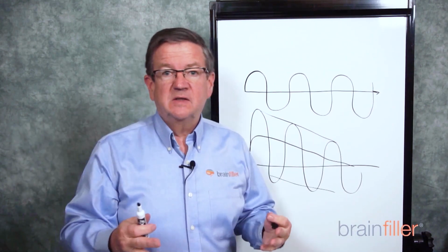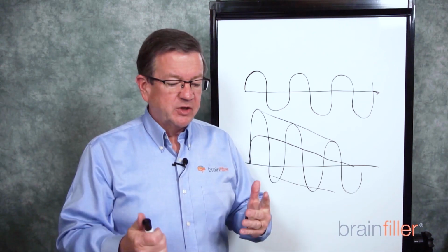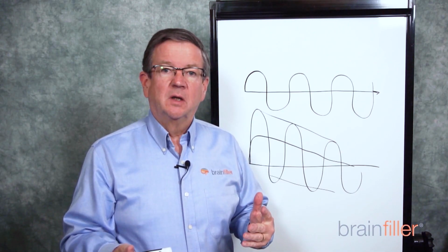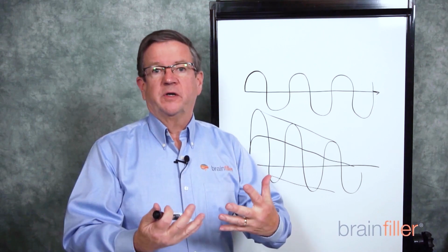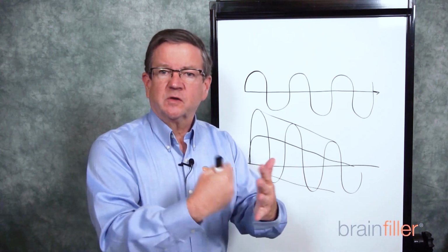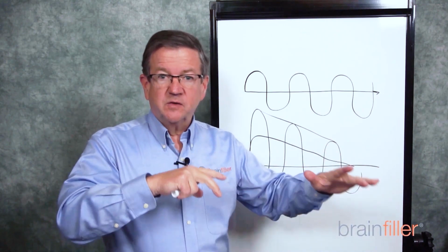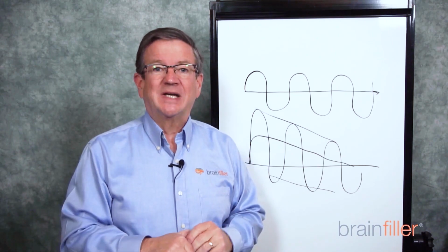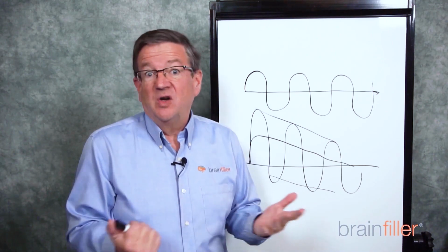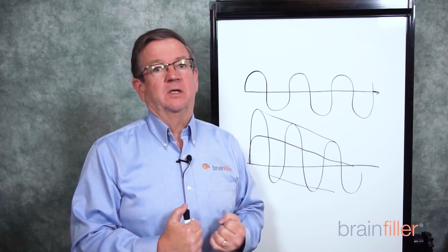Now, where that DC component comes from, you might have heard of it before, but where it actually comes from is when you have a circuit under normal conditions, just serving normal load current, and somewhere out of nowhere a short circuit occurs. The circuit itself, the conductors, the transformers, everything that makes up the circuit is highly inductive. The load's not. The load's mostly resistive. But the circuit is extremely inductive.